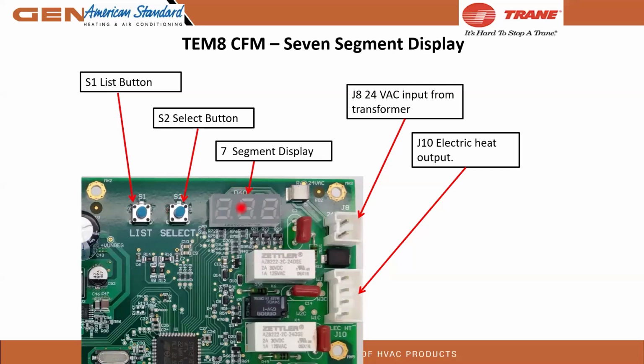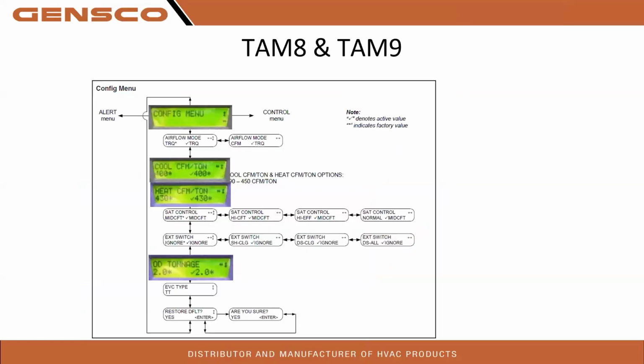So you're going to go list. It's going to go down the flow chart, press select to go right, choose, press list to go back and save. So list. If that was at 350, we'd press select till we got to the 400 and then press list again and it'll save that 400.